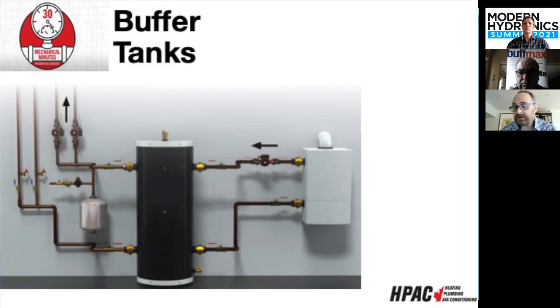And what a buffer tank enables is it lets the boiler run and get into that full state efficiency by running, warming up, and modulating into a nice level area. The buffer tank lets it do that because it doesn't short cycle and turn off. If it's making heat faster than we can use it, it's going to turn off and on again. We call that short cycling. The buffer tank is like a flywheel. It gives the boiler a load that it can work against and heat up, and then be off longer, which leads to greater efficiency.